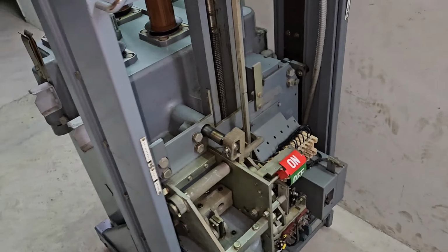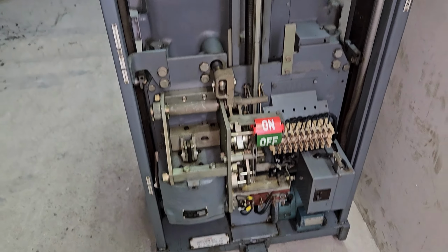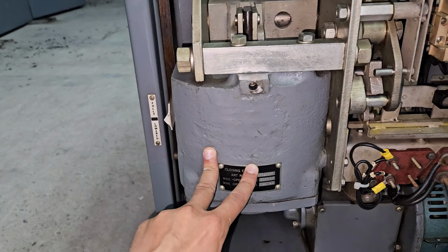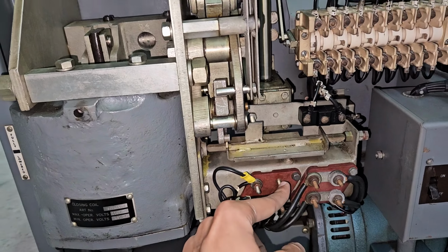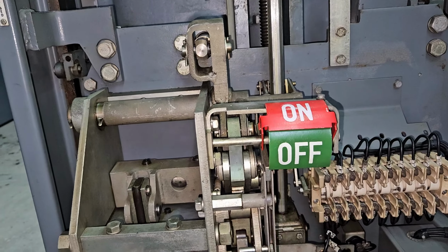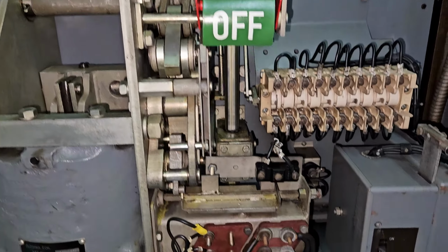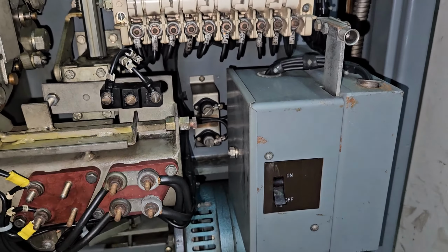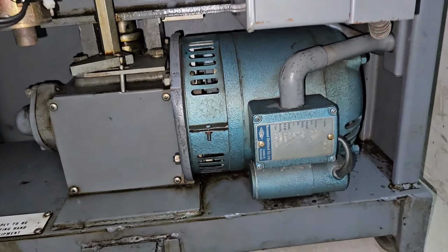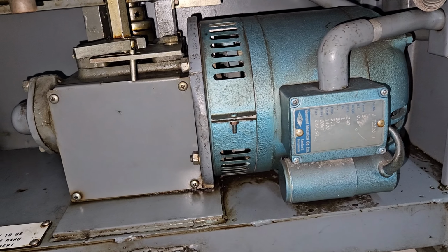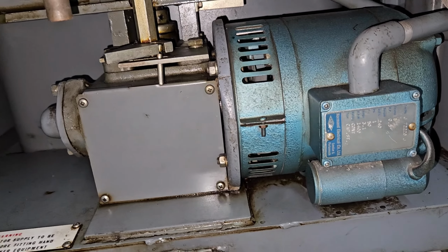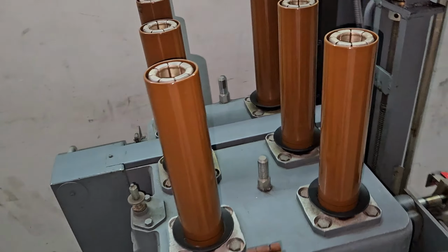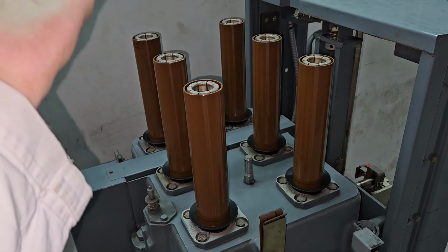Here there is a control mechanism, and this is a closing coil, this is a tripping coil. Here we have an indication for on off status, and this switch is to switch on and switch off power supply for this motor.